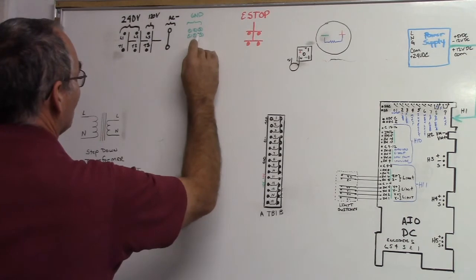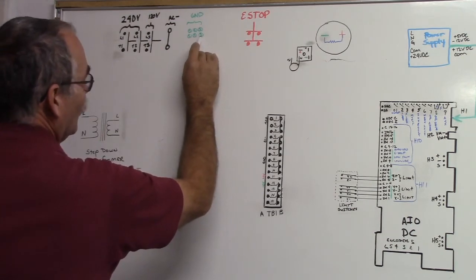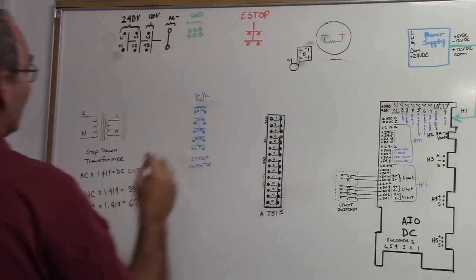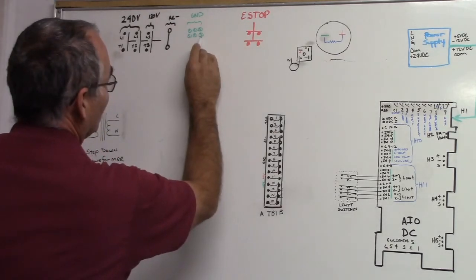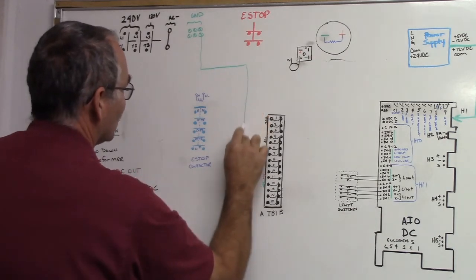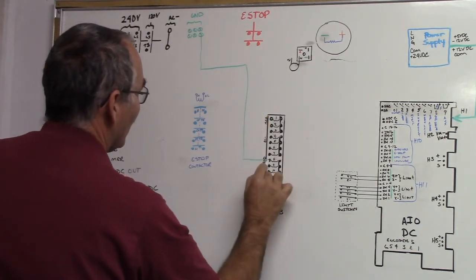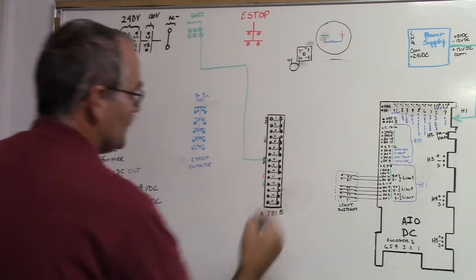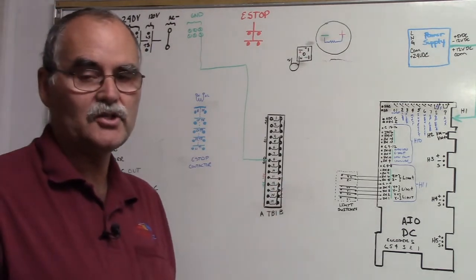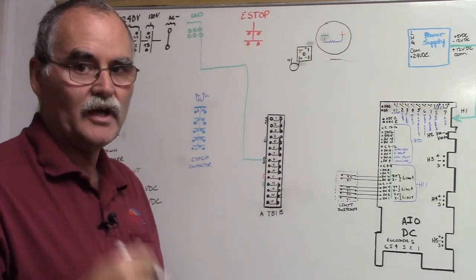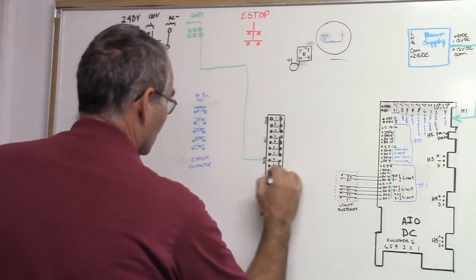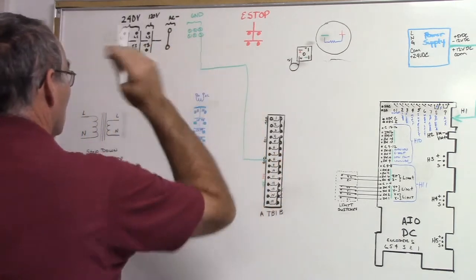So from this ground point you want to go over to TB1-8a. So it's TB1, here's our ground, we're going to come down to 8a. You notice these are all tied together, so any shields from your control cables, anything that's got a drain wire, you want to bring them all back to this point here.